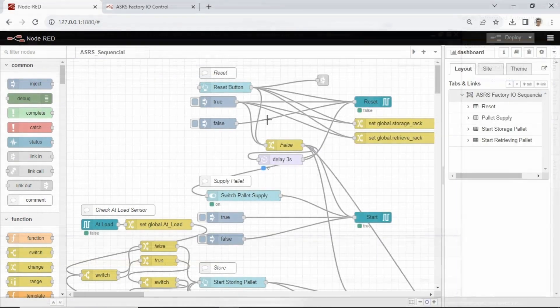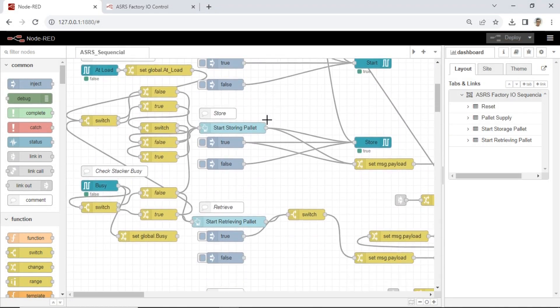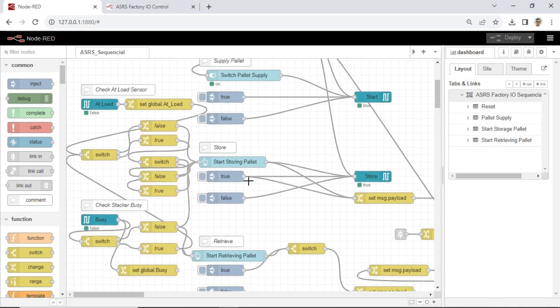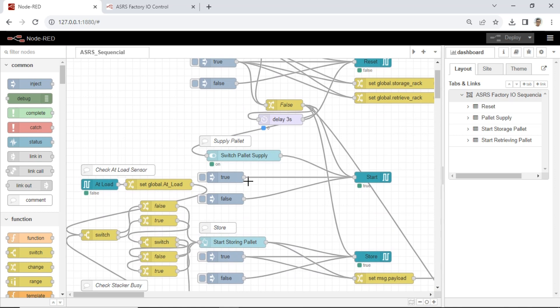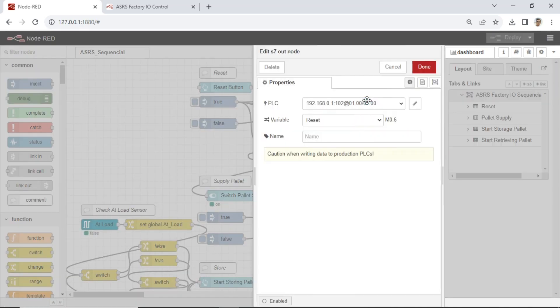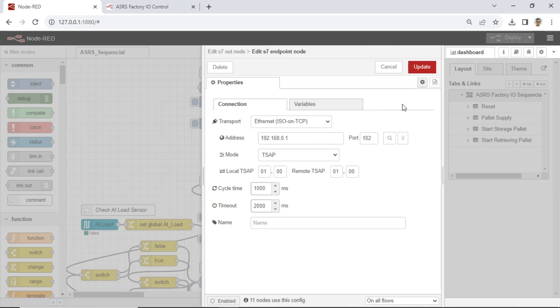This is the Node-RED flow. I'm using the Node-RED Contrib S7 to communicate with a Siemens S7-1200 PLC. Here's the configuration for the connection to the Siemens PLC and the variables that I'll be reading and writing. This allows us to control the ASRS Warehouse.